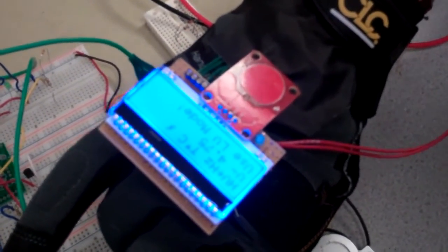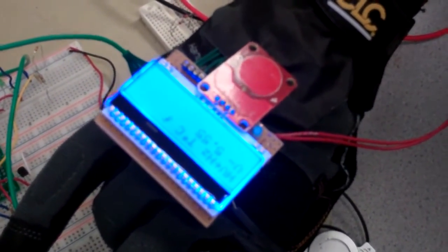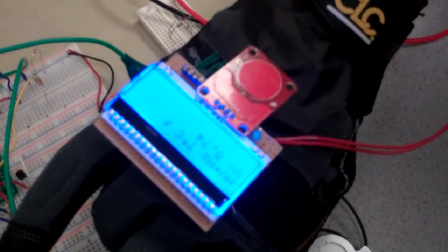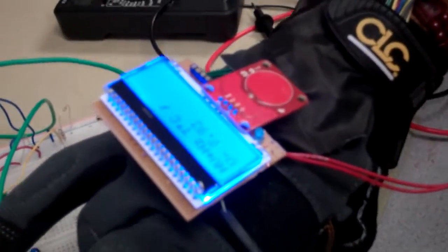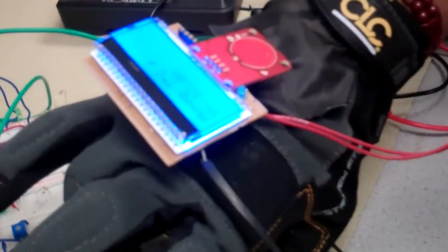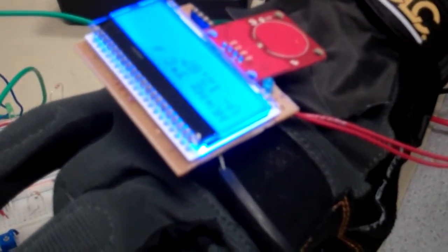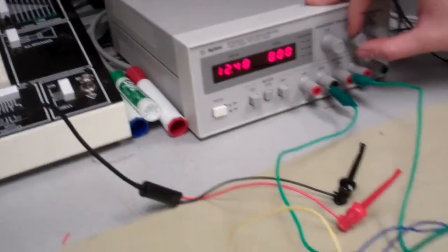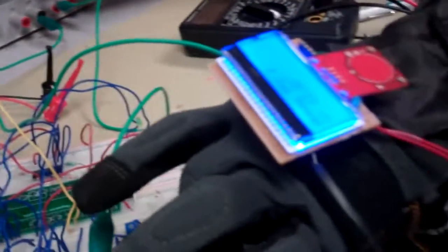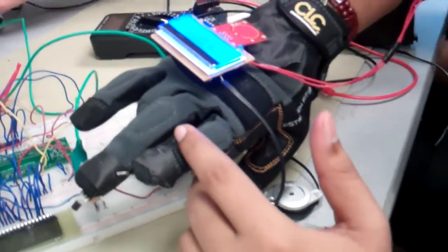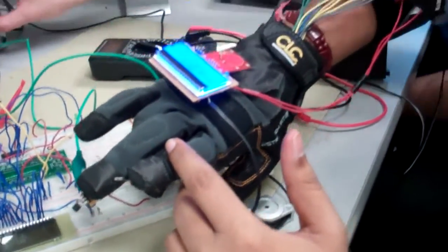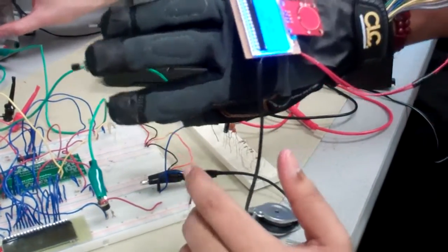Turn it up higher. So, we need to switch... We are having a different profile high voltage. So, if you just plug that in. And then you have to change the mode to high. There we go. So, if it's below 5, it will give you use low voltage mode for more accuracy. For more accuracy. So, we're using a divider on that probe. That's basically it. And then you can go on. Increase more. So, now stop right there for a minute now. You're sitting at 12.87 on here and 12.48 there. So, you're within a percent.